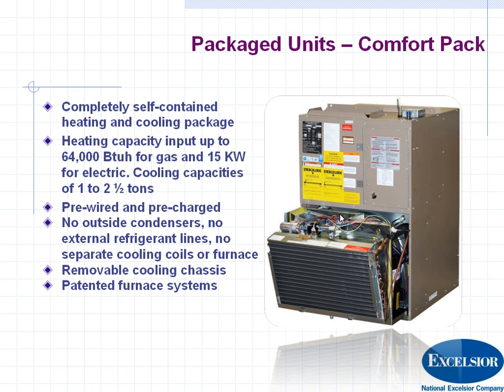They're pre-wired and pre-charged, so no charging out in the field, and you don't need any outside condenser or refrigerant lines, so you have much more security. Removable chassis. This chassis down on the bottom is removable, and what a lot of people do is if they have to take this up to multiple stories, this chassis is removable that they can take out. They just bring the burner section, which is on top, and the fan up in one trip, and then they also bring the condensing unit and the cooling section up in the next trip, and then they put it together upstairs. So that's one little reason that you can kind of split this up. It's easier to put in that way for existing units.